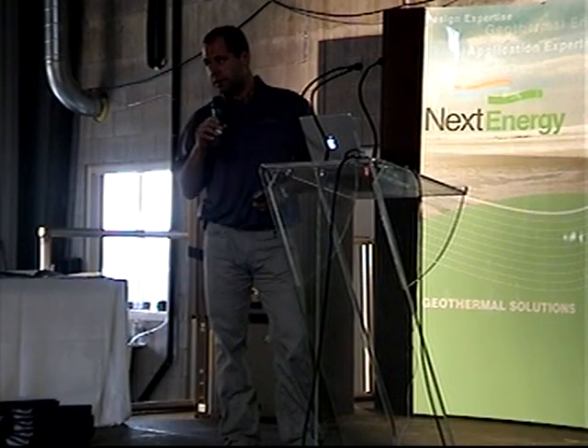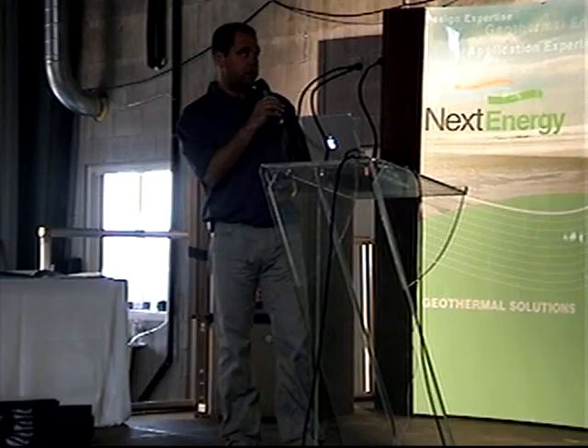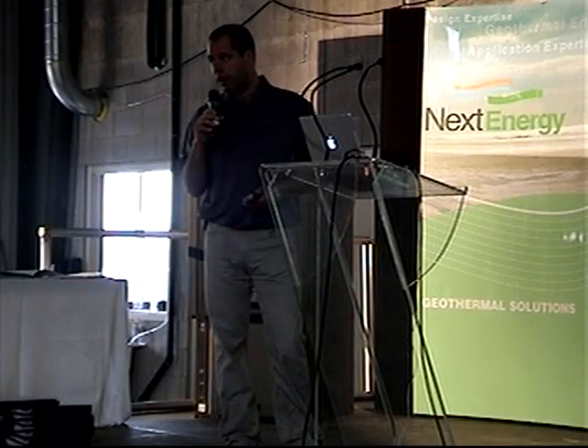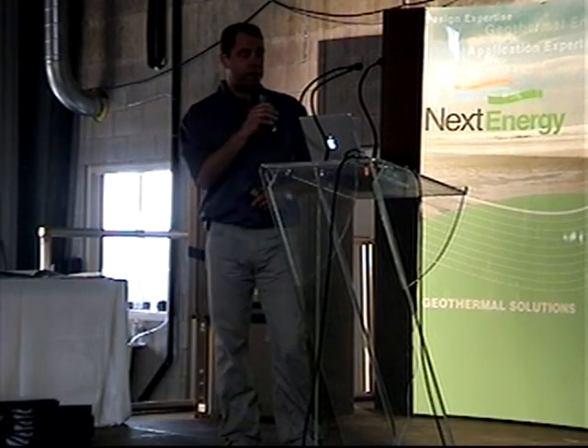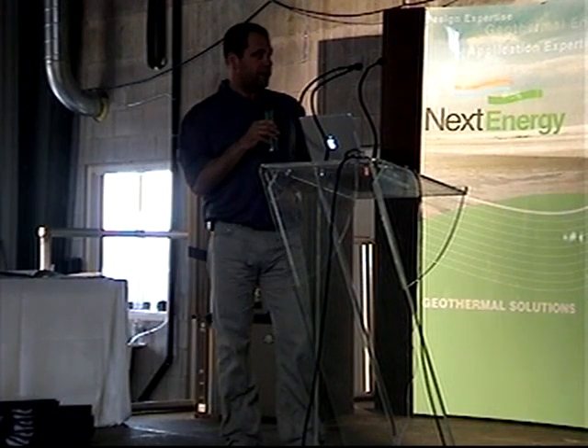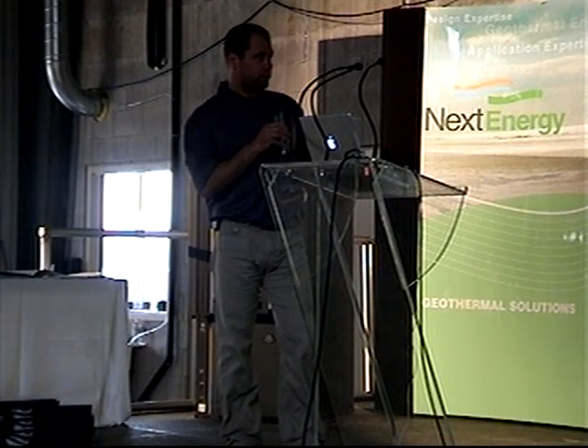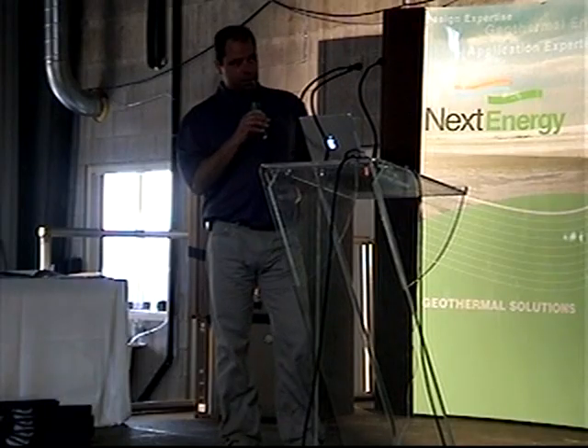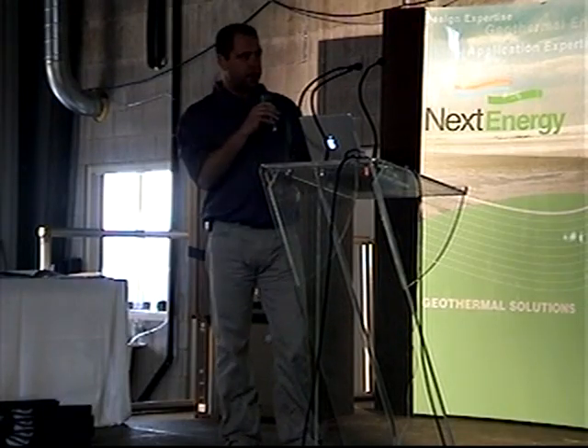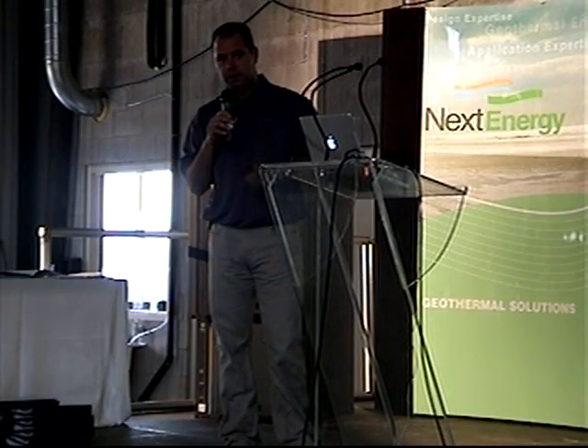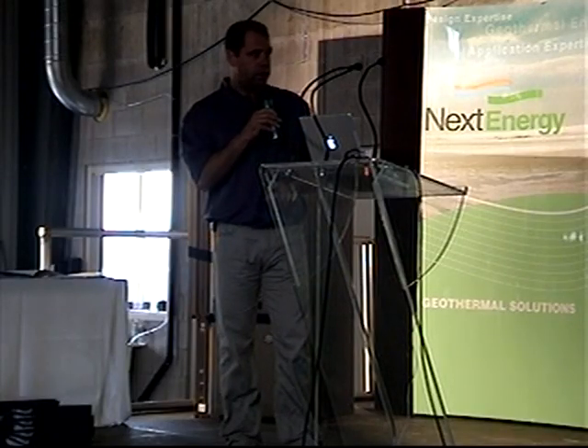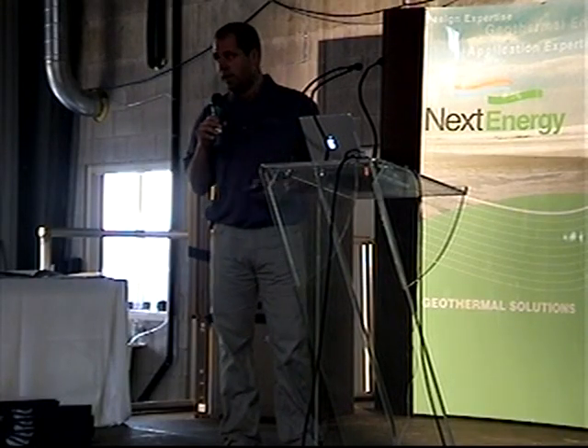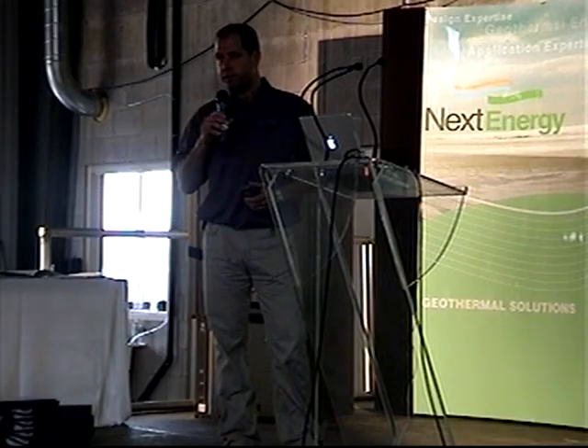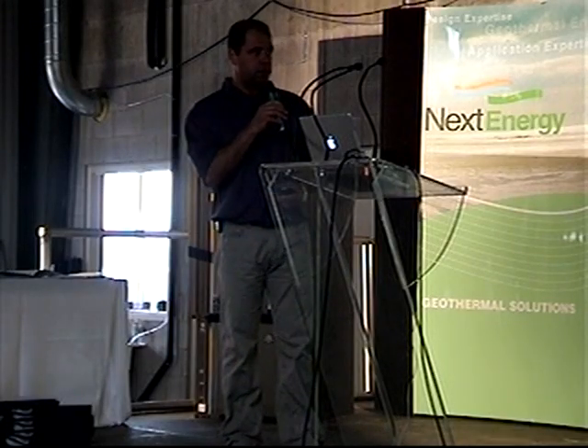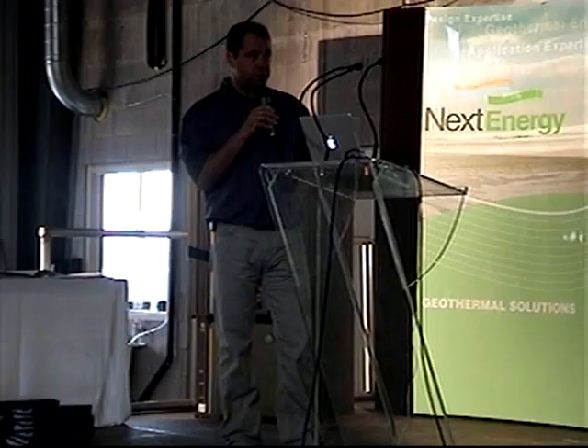Do not put traditional gauges on a 410A system. You will blow the line, or you could blow the line, and that hurts a lot. It requires new production design, hence the Tranquility unit over here. Piping has to be different. The piping has to be stronger to carry the higher pressures. The coils are different. Everything's different about the unit.